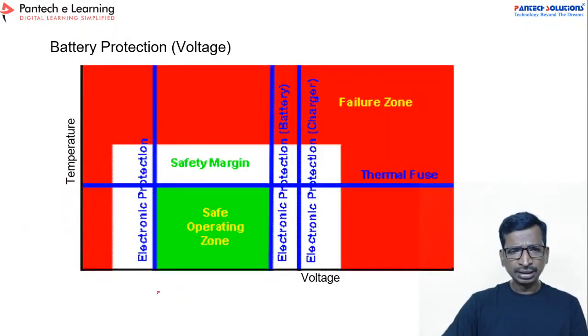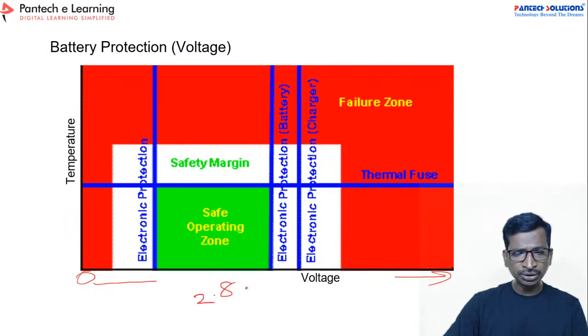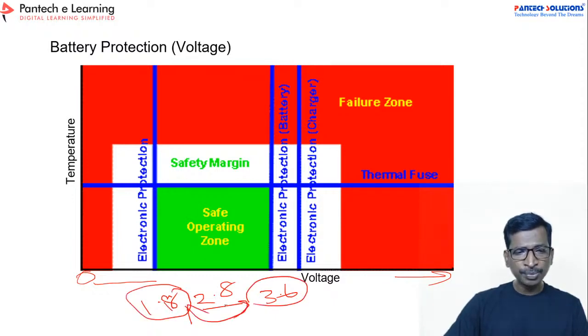Similarly for the voltage, see here, the voltage should not reach zero as well as the maximum voltage. So it should always keep varying with the open circuit voltage. Suppose you take 2.8 volt per cell open circuit voltage, in that case up to 3.6 and down to 1.8 volt. So within this 1.8 to 3.6 volt range, you have to operate. While you are operating within this range, your battery will be in the safe zone. Otherwise, it's a failure zone. So like that, you have to identify your logics in the BMS model.